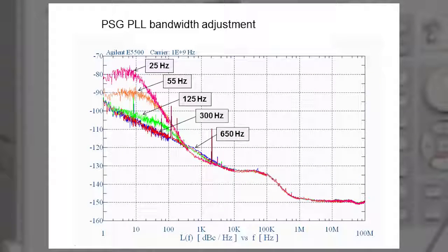In addition, you can tune the phase lock loop bandwidth in the PSG to trade off phase noise between 1 hertz and 1 kilohertz offsets.